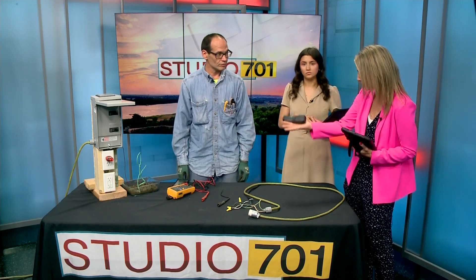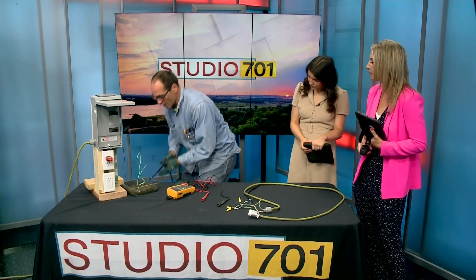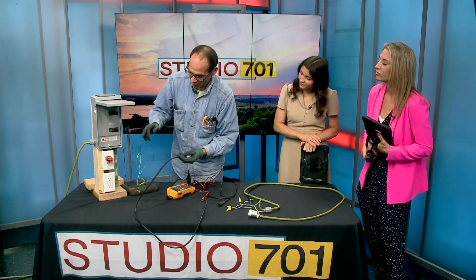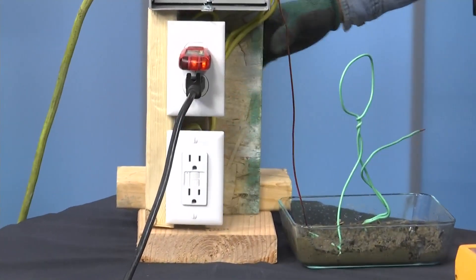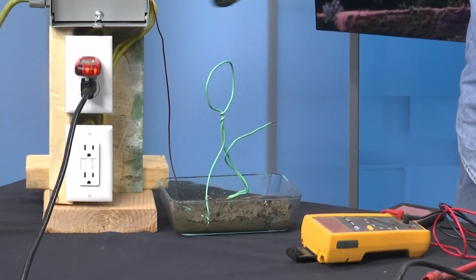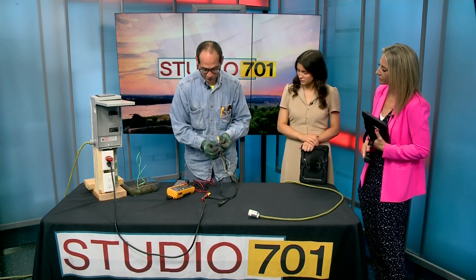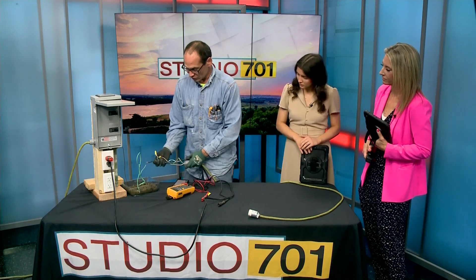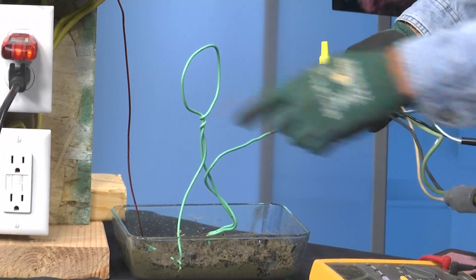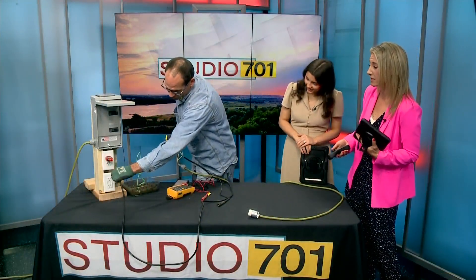This is the kind of experiment that's going to demonstrate to us how this protects you and keeps you safe. So we have wire nuts falling out of my pocket, but that's normal for an electrician. This is just showing that we have power on that outlet right now. If we take this — and I should mention that this is representing a ground rod, which every electrical panel is going to be connected to the earth — this is a way that you could complete the circuit. Don't try this at home because that is live power. It's not tripping the circuit breaker. We still have power here, but that power is flowing through this little person. That would be very dangerous — not good.